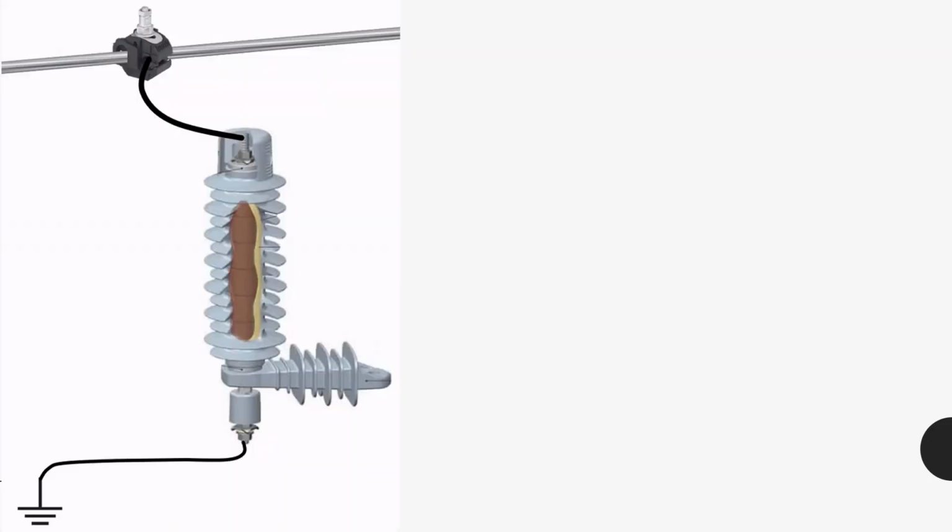Out of these, my preference is for disconnector, as the performance of this component is verified as per IEC 60099-4 for a specific energy discharge class. Hence, it can serve the job. The disconnector will disconnect the arrestor from power lines before the arrestor fails.